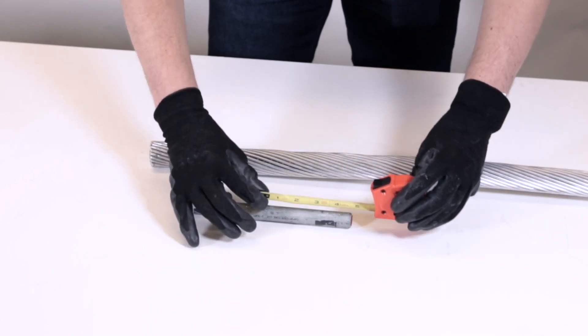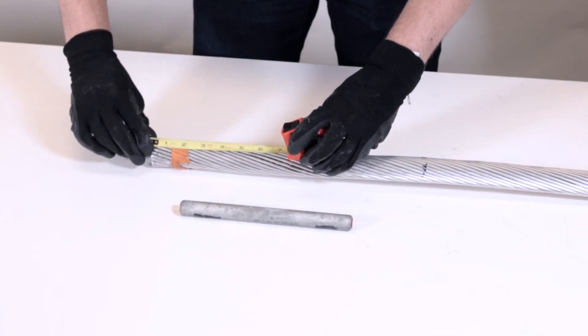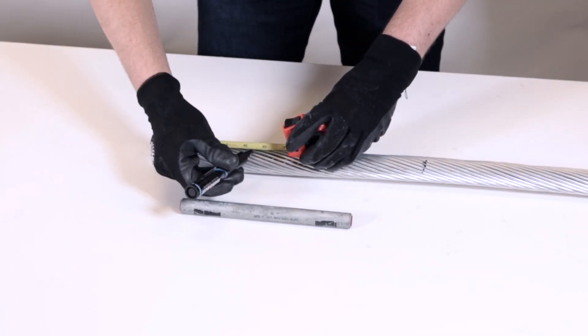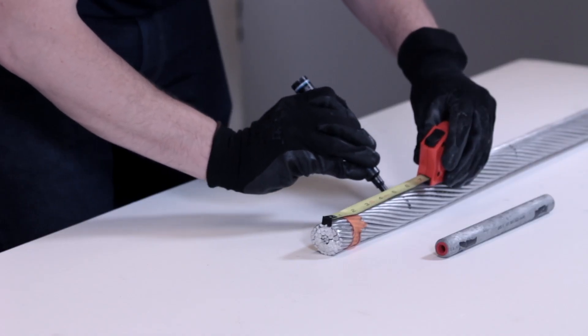Measure from the knurl in the middle of the galvanized steel splice tube to the end. Add one inch to this length to allow for aluminum strand expansion when the splice tube is applied. Mark this length on the conductor as the point where the aluminum strands will be cut back.